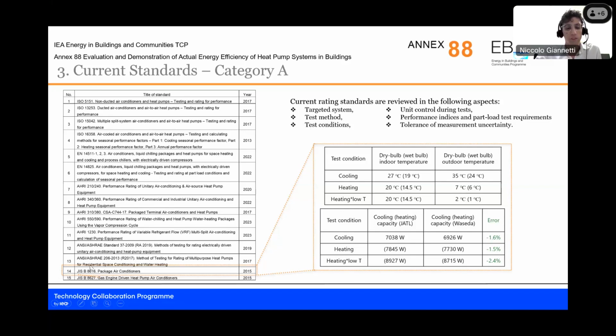Below, I report a simple example of some results obtained according to these Japanese standards, just to give an idea of the level of reproducibility required. This is the result of an interlaboratory test. Two different facilities tested the same unit and obtained results that are consistent within 3% error, which is also a requirement of this test. For other requirements, I think AHRI 210/240 requires 6% error. This is just a reference to compare with the following results of category B standards.